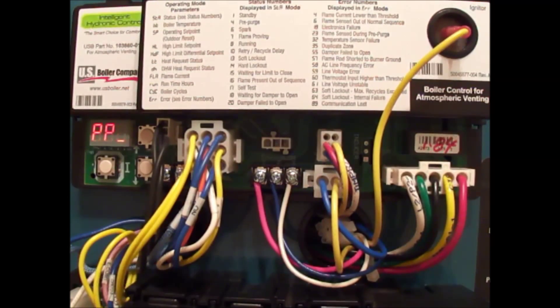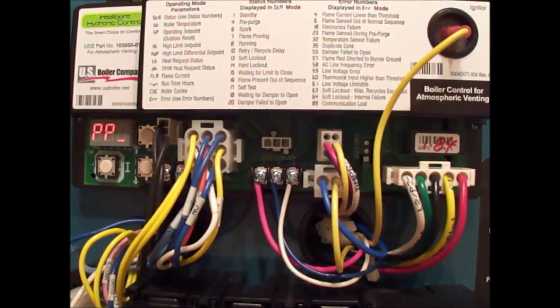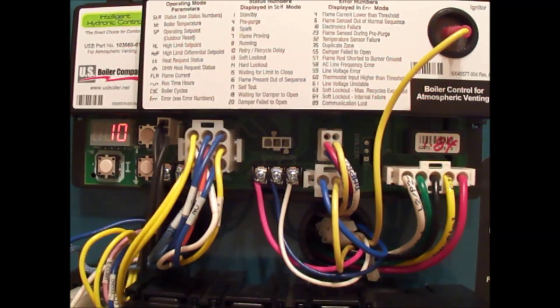I'm going to want this boiler only to fire if the temperature drops low enough. So I'm going to put more minutes in that pre-purge to try and keep the boiler off as long as I can and just bring it on temperature only.